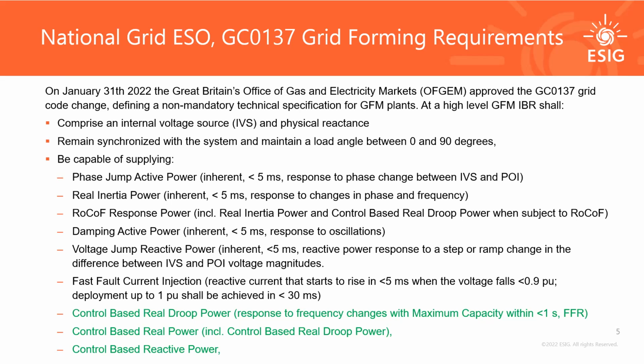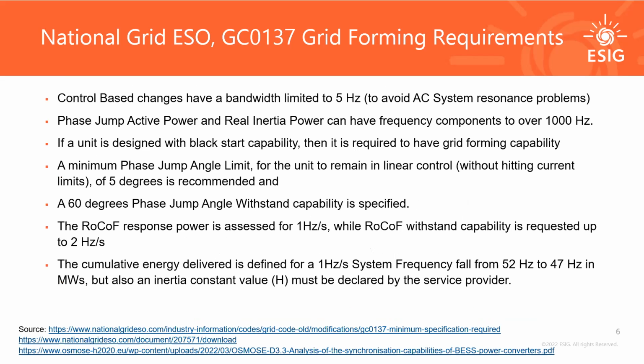One thing to add is that in all of the specifications that are out there, grid forming capabilities are on top of the requirements that already apply to grid following inverters. So everything that's already been developed, say in IEEE 2800, which was mentioned yesterday, in this type of specification for grid following inverters, also applies to grid forming unless there is some kind of conflict between grid forming capability and what's in the requirements for grid following inverters.